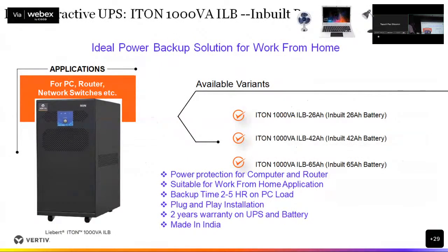Apart from that, we have also launched an ILB line interactive UPS supporting up to 200 Ah battery. This UPS is most helpful for point of sale applications, wherever in remote sites you want even 16 hours of backup for 100 watt small equipment. In a remote site where you have a maximum of 8 hours of power, you want a backup of 16 hours - we can give a solution for 100 watt load. This machine is capable of charging up to 200 Ah battery, either SMF or tubular battery, so you can still keep those sites running without a DG.